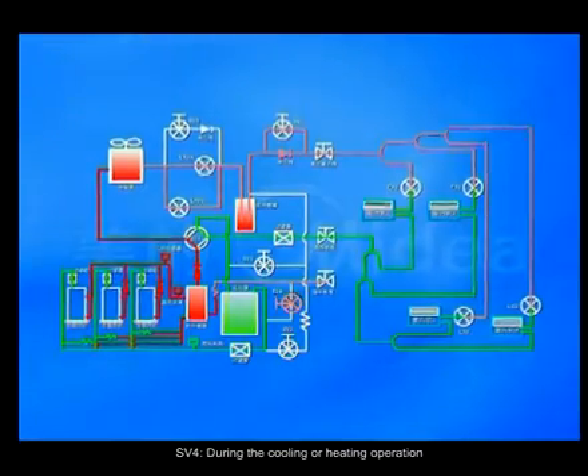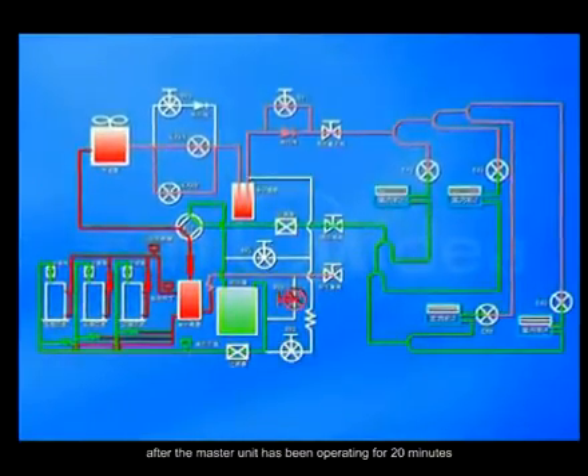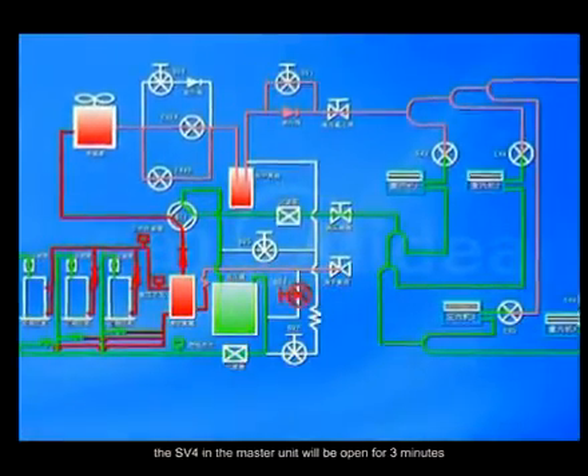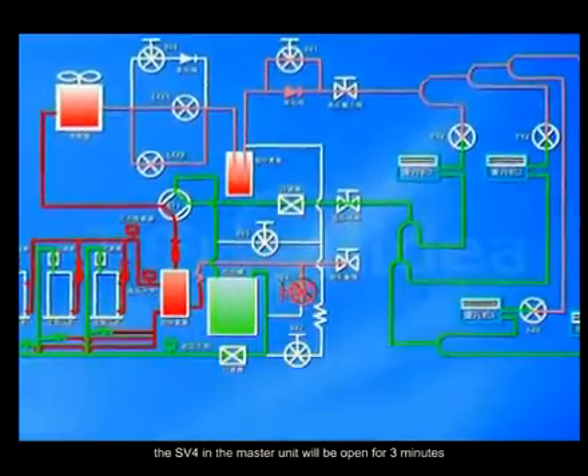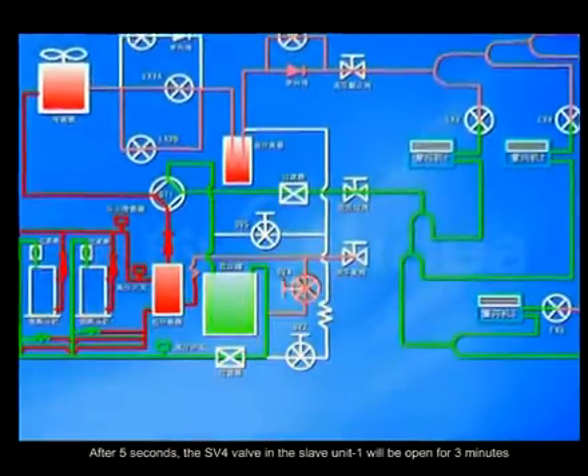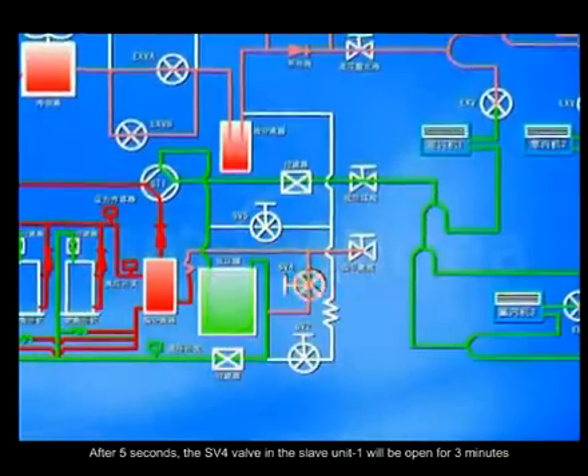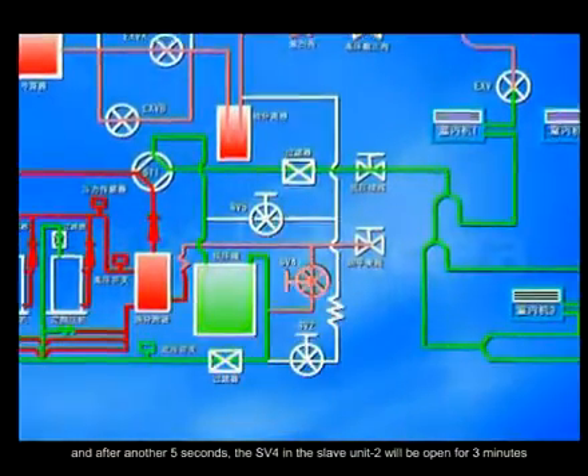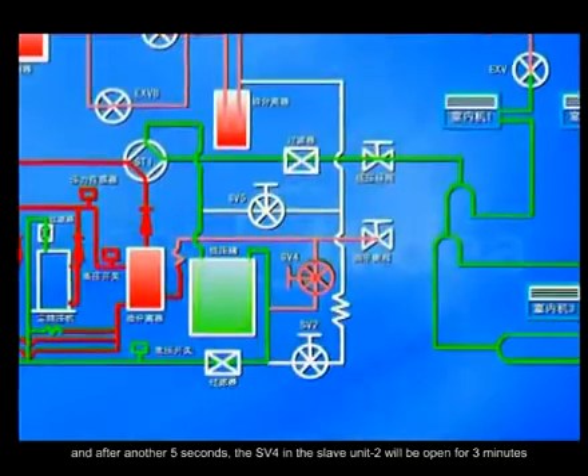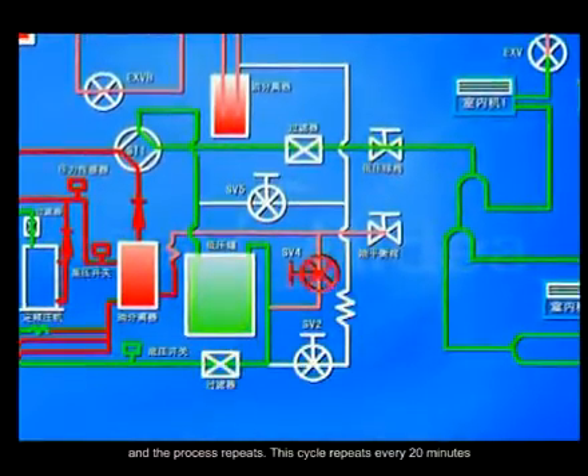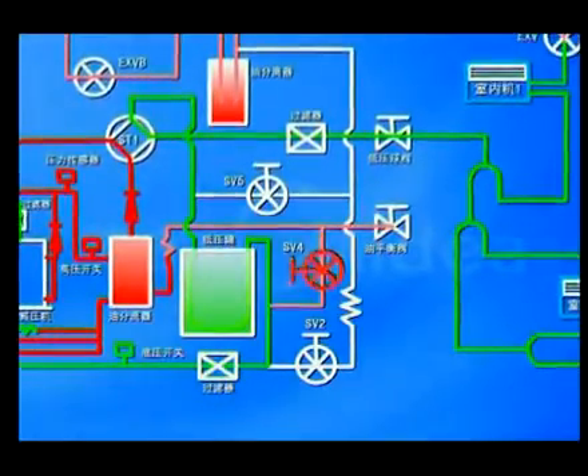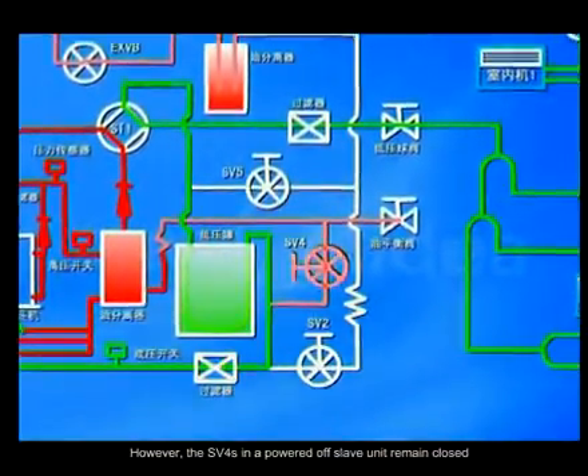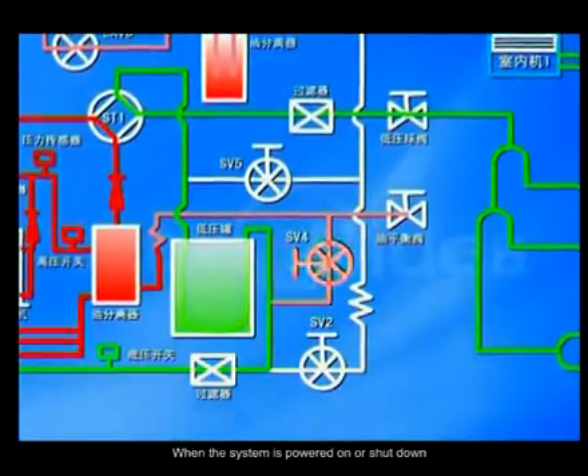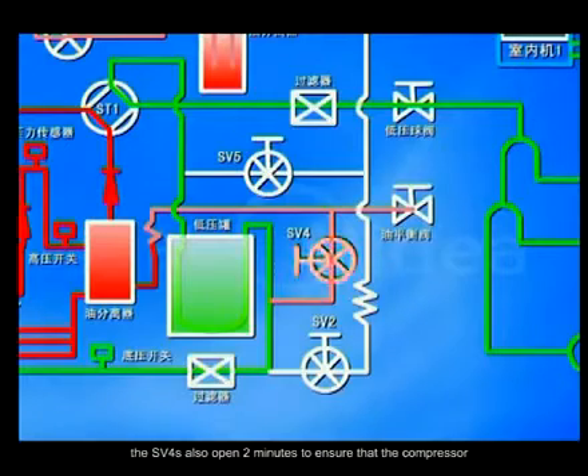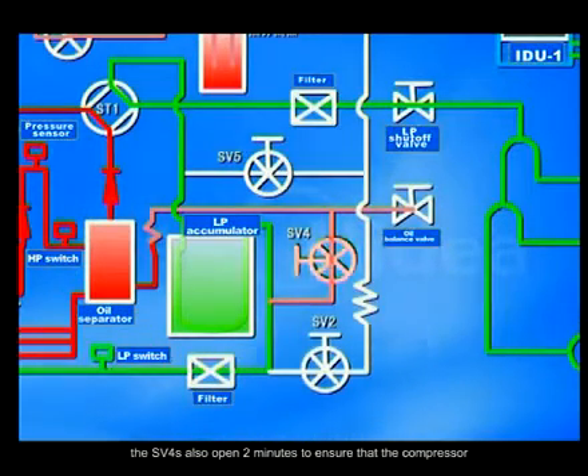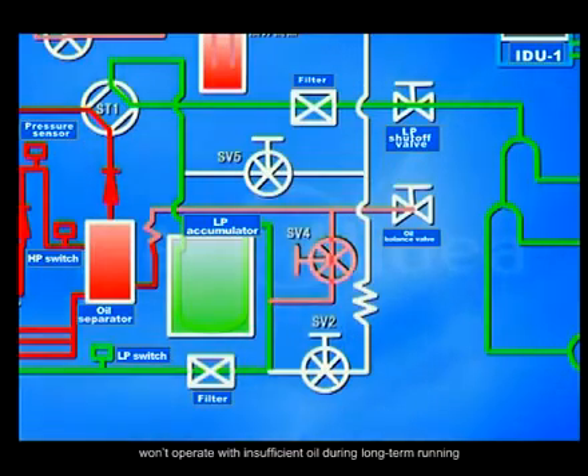SV4. During the cooling or heating operation, after the master unit has been operating for 20 minutes, the SV4 in the master unit will be open for 3 minutes. After 5 seconds, the SV4 valve in the slave unit 1 will be open for 3 minutes, and after another 5 seconds, the SV4 in the slave unit 2 will be open for 3 minutes, and the process repeats. This cycle repeats every 20 minutes. However, the SV4s in a powered-off slave unit remain closed. When the system is powered on or shut down, the SV4s also open for 2 minutes to ensure that the compressor won't operate with insufficient oil during long-term running.